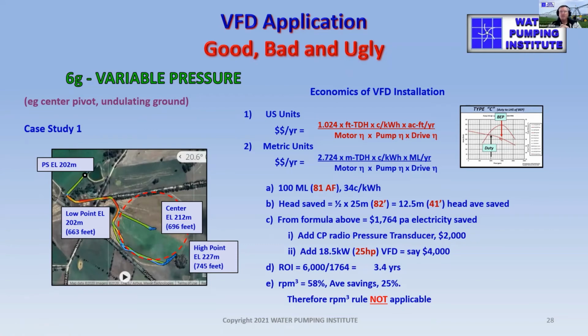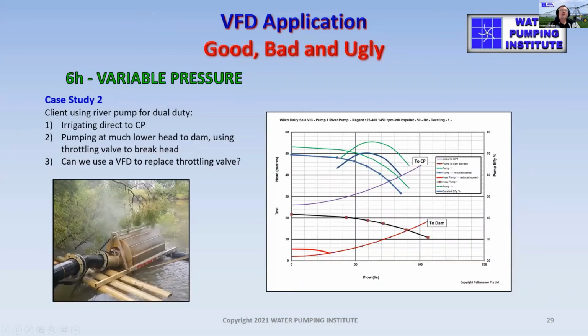However, it does point to the fact that the RPM rule does not apply here. It applies for a specific elevation, but overall your savings do not equate to the RPM cube rule, as the VFD industry would tell you. What about a situation where a pump is delivering much higher head than is required, and the irrigator puts in a throttling valve? It might be a butterfly valve or a gate valve, or even a hydraulic valve with a bonnet and a membrane. We normally regard those throttling valves as energy wasters, and if we can do away with them, all the better.